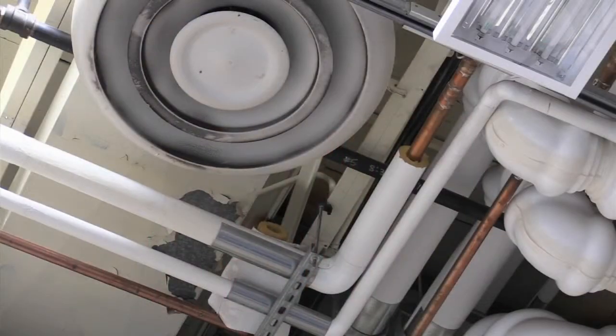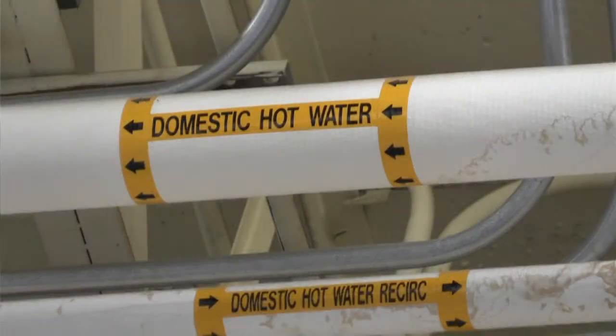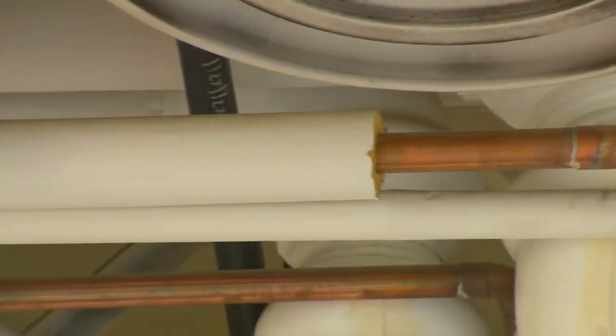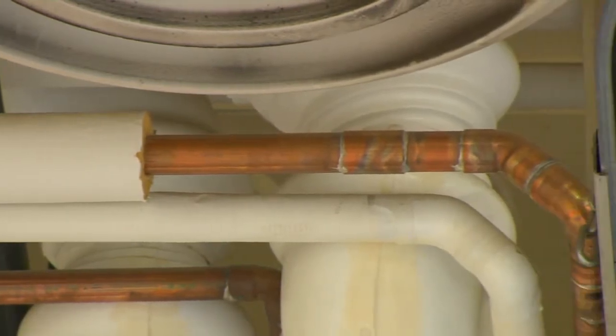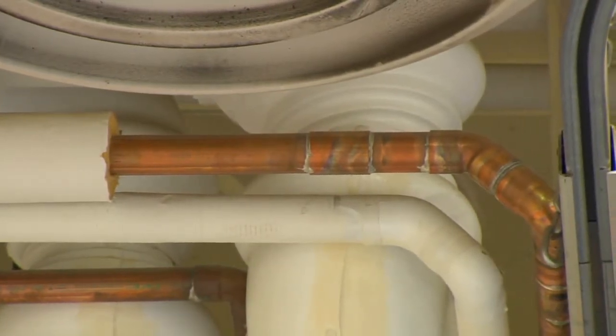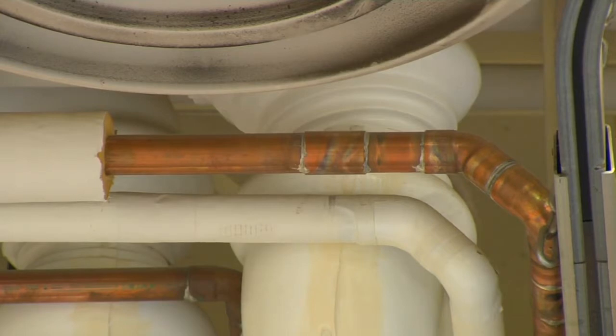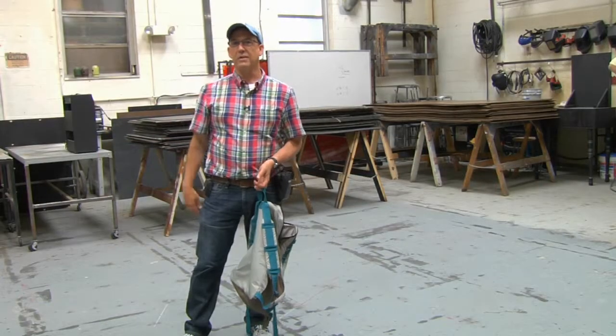If you look up here to my right, you'll see some uninsulated pipe. The compressed air obviously is uninsulated. If you look real close, you'll see some domestic hot water. It looks like at the unions or at the 90s or the T, they had to remove the insulation and resolder some pipe. The insulation was not replaced. That happens all the time.